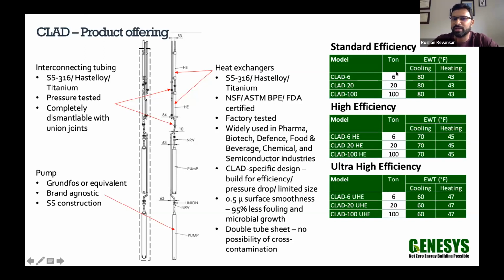Like I said, on the open loop side, it only needs about 1 GPM per ton. So a CLAD 6 would need 6 to 7 GPM on the open loop side. But on the closed loop side, it could have your 18 GPM, which is 3 GPM a ton. We see CLAD 6 as the unit that is going to be used in most small residential systems. Then there is the CLAD 20 and a CLAD 100. And these were specifically picked for the sizes of most geothermal projects that we would be working with. And we have a CLAD 50 on its way as well. And that should be available later this year.